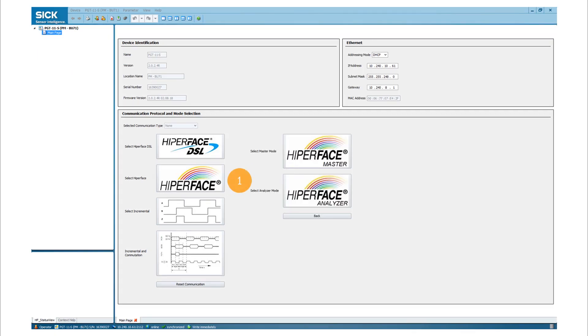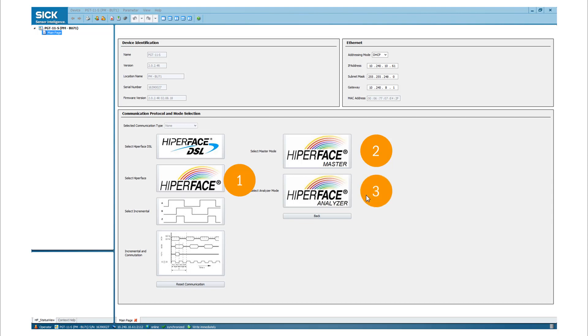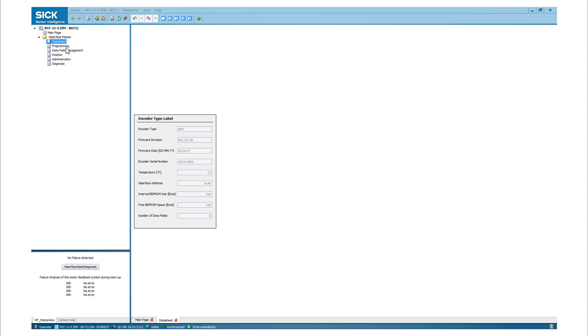After clicking on the HIPERFACE icon, you can choose between two modes. The HIPERFACE master mode offers functions for setting and reading positions, data field management, and others. The core function of the HIPERFACE analyzer mode is to check the sine and cosine signals of the sensor. After selecting the HIPERFACE master mode, the tab data sheet appears after a couple of seconds. It depends on the connected sensor and its firmware which tabs are available.